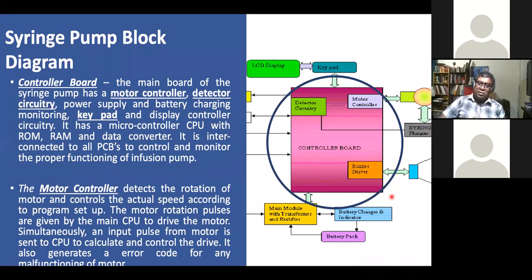So when you talk about the control board, it is the basic thing that every electronic medical device has. The control board monitors every single change of signal, and any sensor is going to send information to the control board. Even the mechanisms are controlled by the control board. For motor control, it detects the rotation and actual speed according to the program set. The motor itself runs on an electronic circuit because it's using a stepper motor. Stepper motors have four step signals, depending on the type of stepper motor used. It sends the information to the CPU, all that. When you set a rate, the stepper motor follows the rate and at the same time maintains the speed.